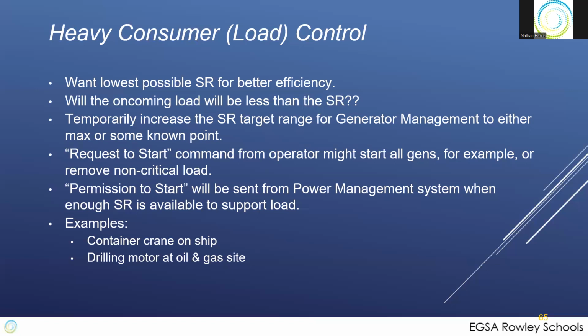Remember what spinning reserve is. You're increasing spinning reserve to a level that will accommodate the oncoming load. The other example we use is a container crane on a ship. The operator climbs up into the crane cab and pushes a request to start button. That request to start actually increases the spinning reserve set point to a point where all the generators start. Once they all start and are on the bus, he's given permission to start. He says, okay, you may now start moving the crane. So he does his crane work, pulls, unloads, or whatever. Once that's over, we don't need that spinning reserve anymore. He shuts the cab door or closes the system down, and our spinning reserve drops back down to a low level again, and it sheds the generators we don't need anymore to optimize our fuel. So that's heavy consumer or load control.